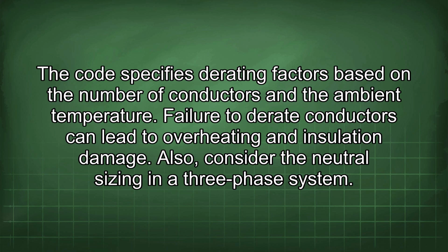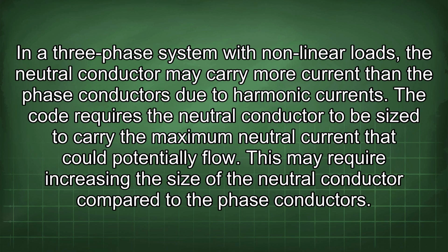Also, consider the neutral sizing in a three-phase system. In a three-phase system with nonlinear loads, the neutral conductor may carry more current than the phase conductors due to harmonic currents. The code requires the neutral conductor to be sized to carry the maximum neutral current that could potentially flow. This may require increasing the size of the neutral conductor compared to the phase conductors.